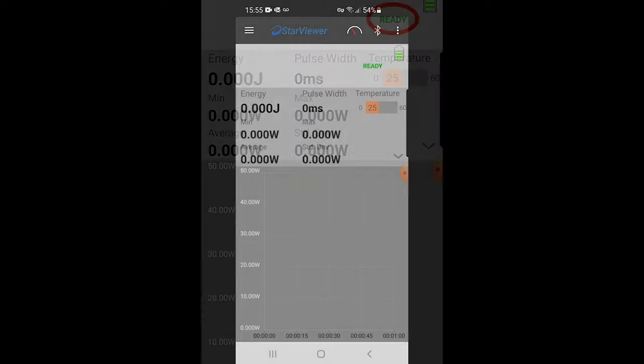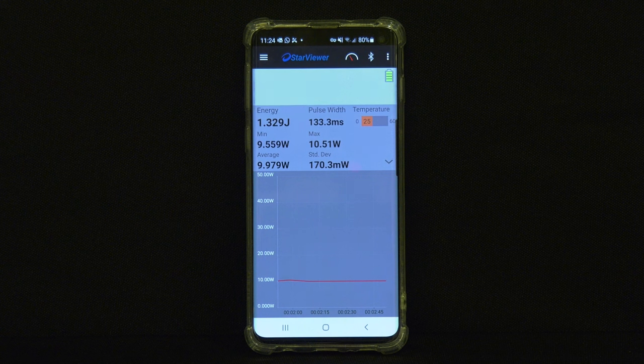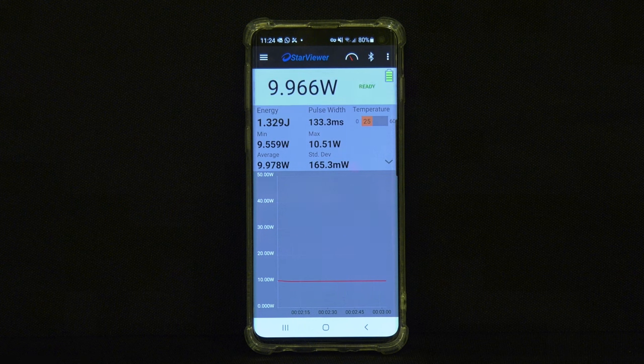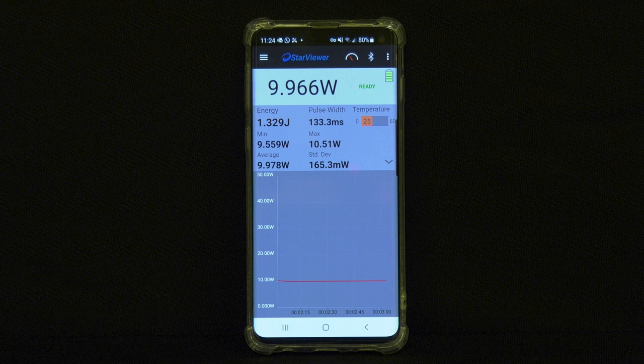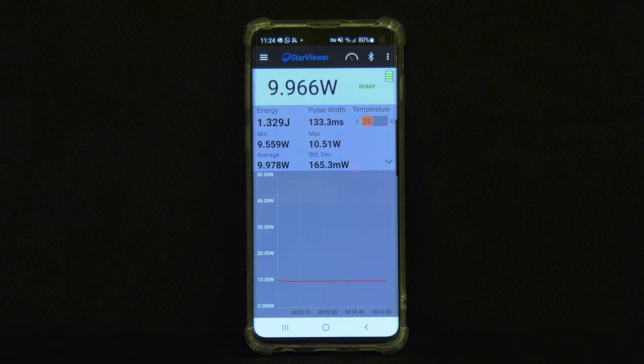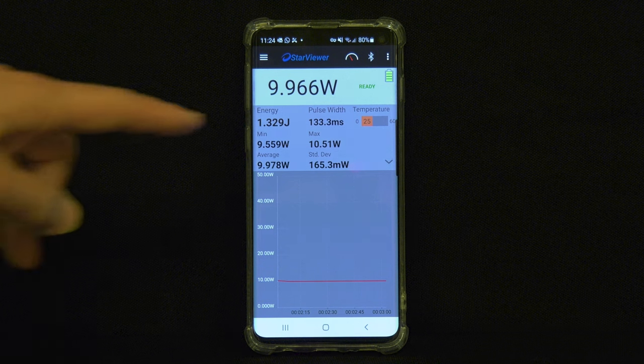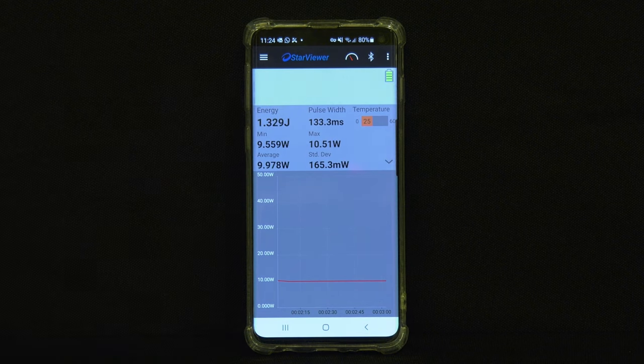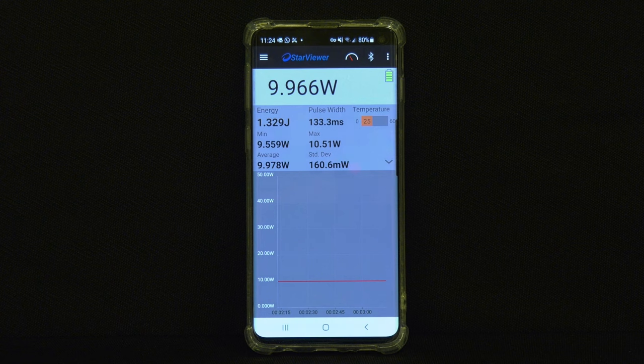In the display window, we see the ready indicator, which tells us that the REL is ready for a laser exposure. When the laser has fired, we get the readout within three seconds of the end of the exposure. Besides the power reading itself, note that we're also shown the measured energy itself, as well as the measured exposure time or pulse width, so that as complete a picture as possible is offered to the user.